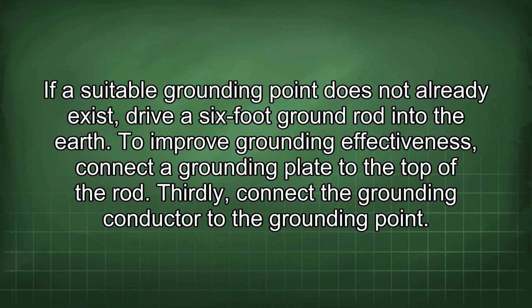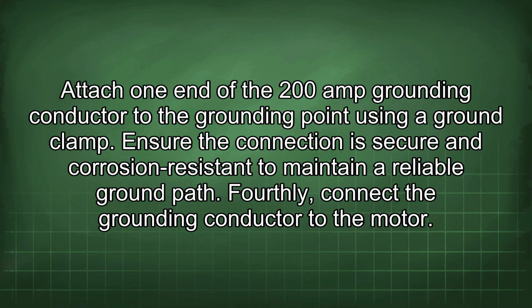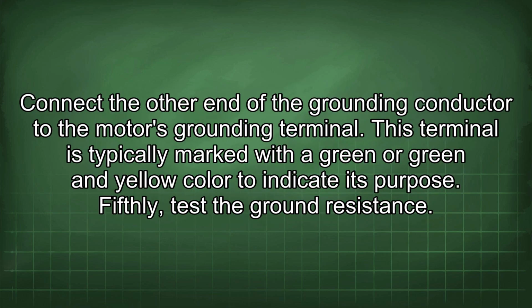Thirdly, connect the grounding conductor to the grounding point. Attach one end of the 200-amp grounding conductor to the grounding point using a ground clamp. Ensure the connection is secure and corrosion resistant to maintain a reliable ground path. Fourthly, connect the grounding conductor to the motor. Connect the other end of the grounding conductor to the motor's grounding terminal. This terminal is typically marked with a green or green and yellow color to indicate its purpose.